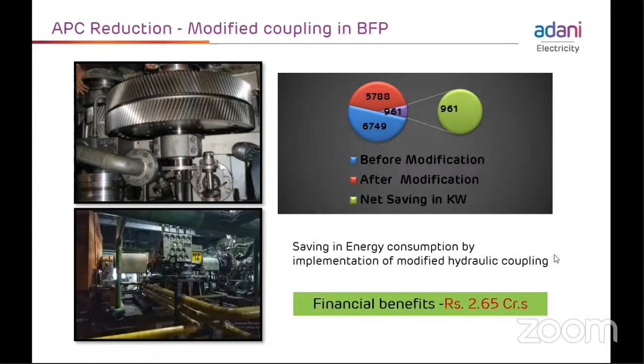achieve 960 kilowatt saving just by replacing this hydraulic coupling, with a payback period of only 6 months, which was costing 1 crore, including service charges. And after the successful implementation of this project, we have changed this hydraulic coupling in all 4 boiler feed pumps.